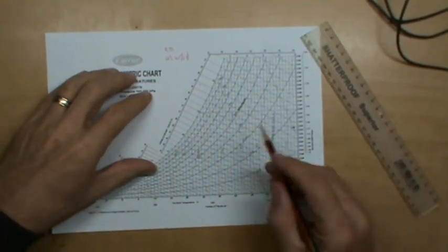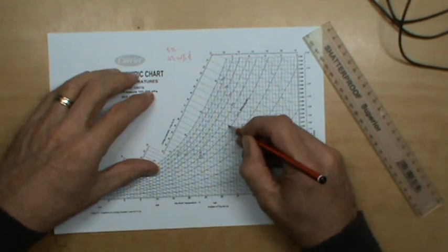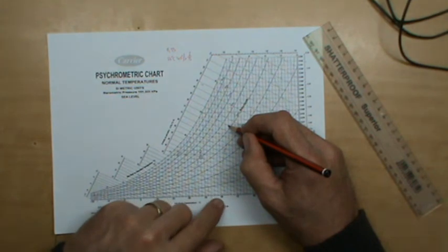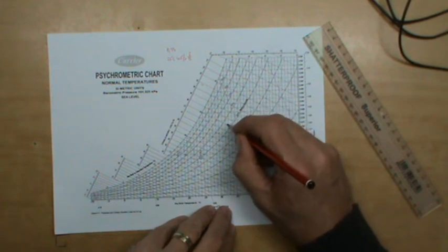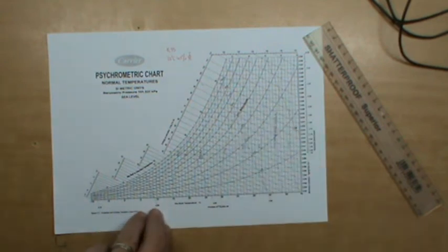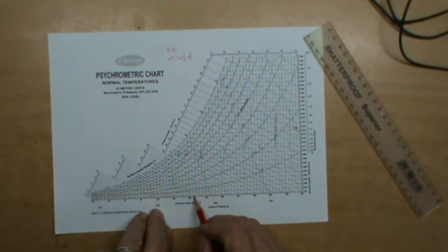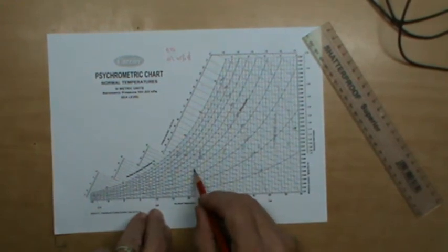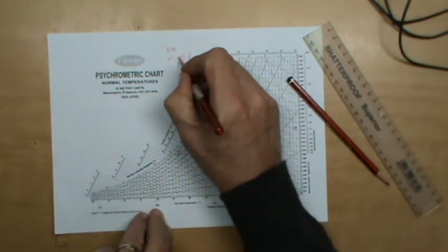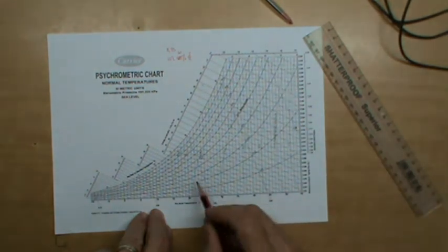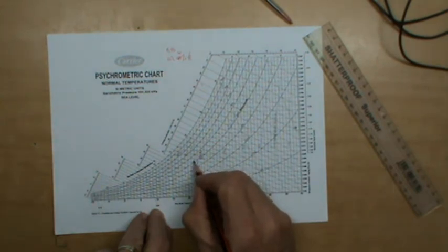So let's say that our outside temperature is 33 degrees Celsius dry bulb, 31, 32, 33, and 25 degrees Celsius wet bulb. That's state point number 1 over there. And that state point 2 is at 22 degrees and 50% relative humidity. Oh, wait a minute, I'm going to change it to 50% relative humidity. Okay, 22 and 50% relative humidity. So in other words, that is where state point 2 is going to be over there.